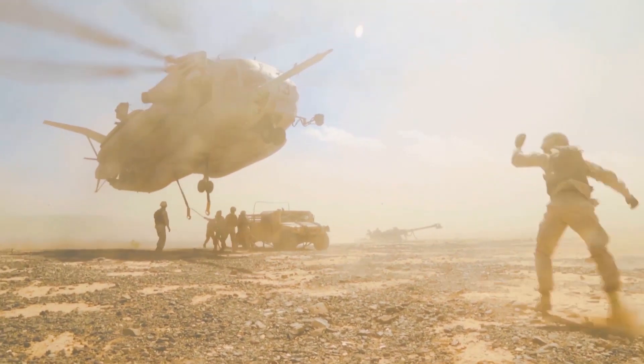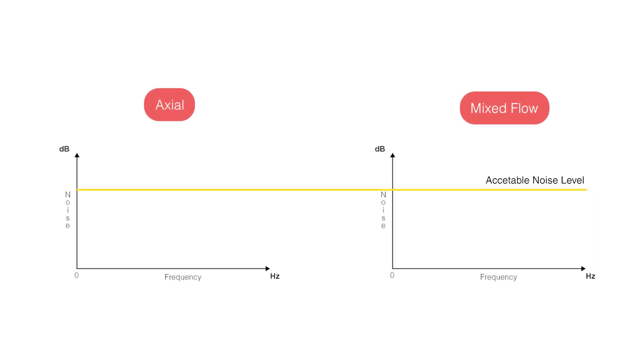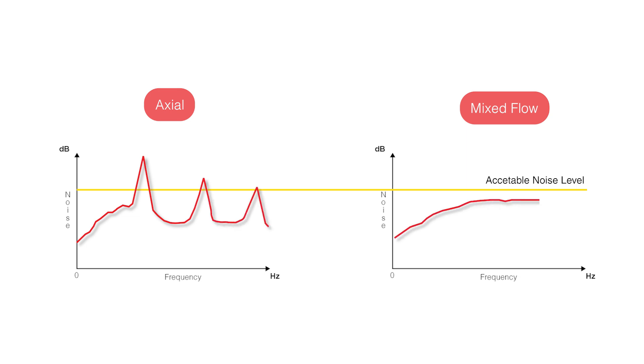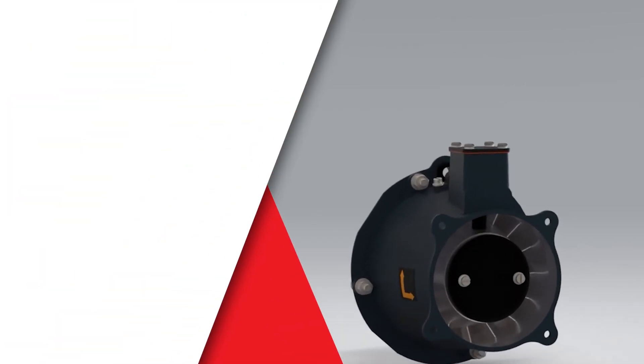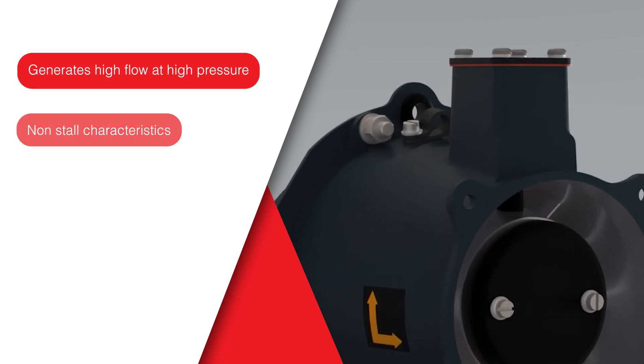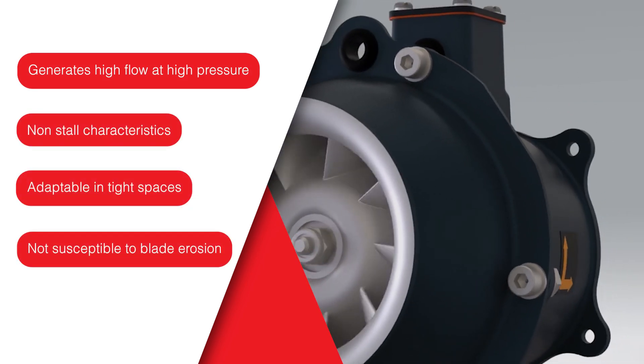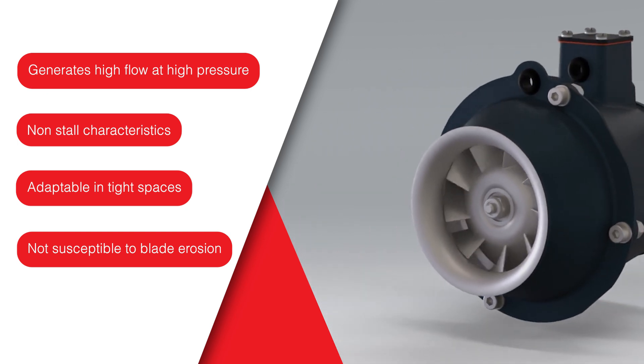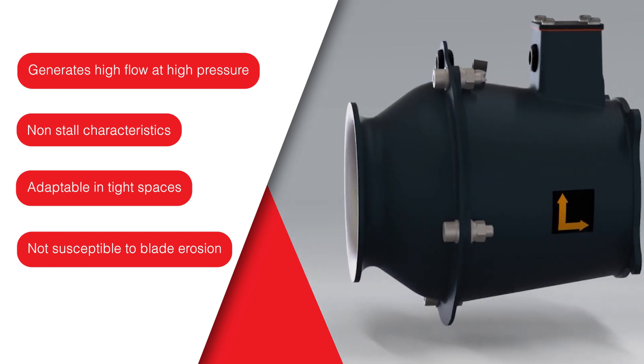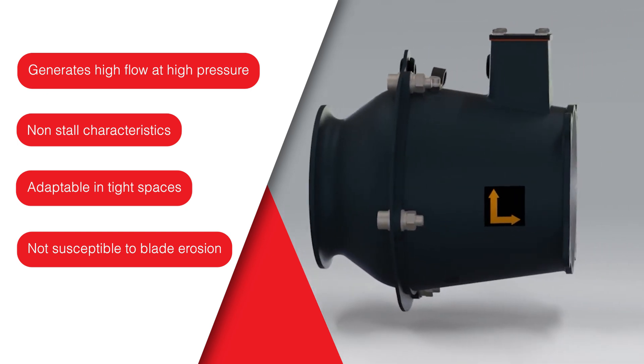Due to their aerodynamic characteristics and lower operating speed, mixed-flow fans are also quieter than axial flow fans, which generate high-pitched frequencies as their blades pass by a stationary guide vane. In summary, a mixed-flow fan can deal with high pressures and produces high flow rates needed for cooling. They are highly adaptable in tight spaces where a clear axial flow path is not achievable, and they are not susceptible to blade erosion, making them a great choice for engine cooling and sand scavenge applications.